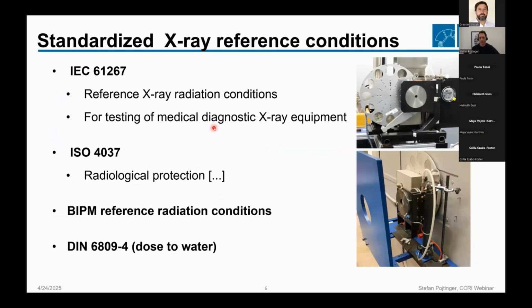If you want to calibrate or test these kinds of devices, maybe in type testing, you need X-ray reference conditions. In general, we have many reference conditions defined for X-rays. For example, in the ISO standard 4037, we have some for the purpose of radiological protection. Of course, we have the BIPM reference radiation conditions we are using for comparisons. Also, we have some national standards, for example, in Germany for absorbed dose to water in X-rays. But I think the most relevant standard for us today and for the project is IEC 61267, because this IEC standard explicitly defines reference X-ray radiation conditions for testing of medical diagnostic X-ray equipment. And that's what we want to do here.